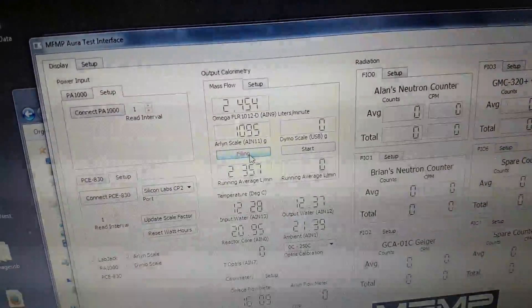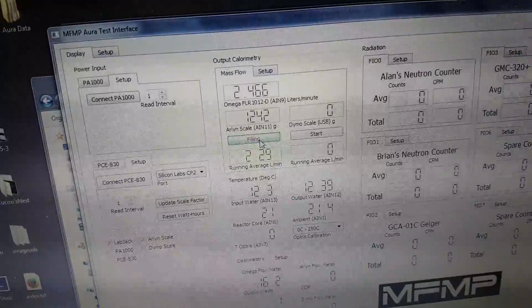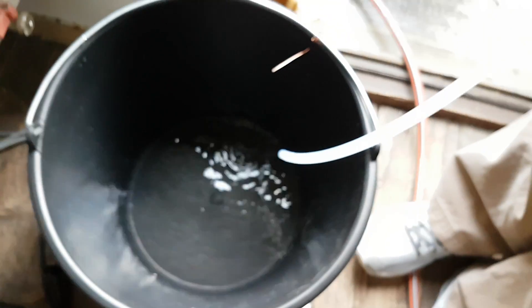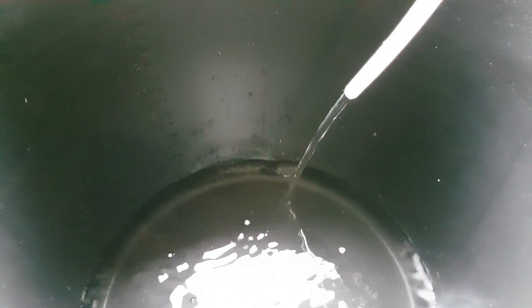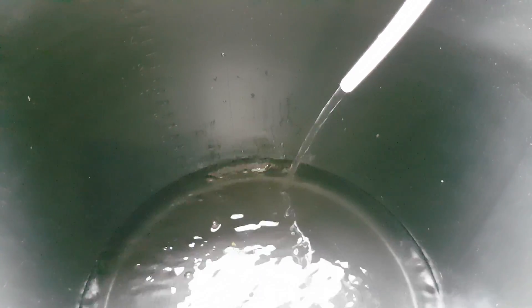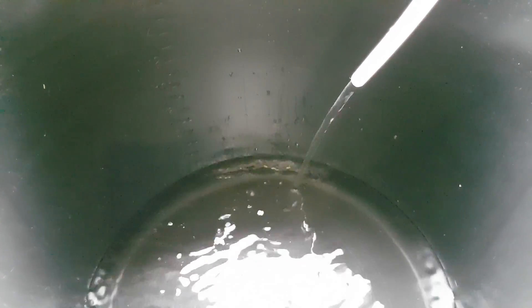Are we measuring temperature now? That changes the water density just a little bit. We're not — well, it's logging, but we're not heating the water. As long as we have the data as a point of reference. Fortunately, the flow meter is on the cold side, which won't vary by more than five degrees, so we'll have very little variation there — as opposed to if it were on the hot side.